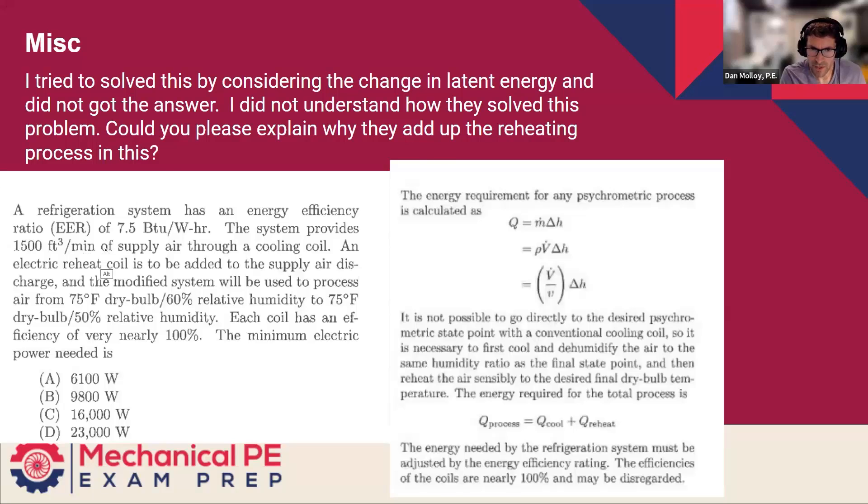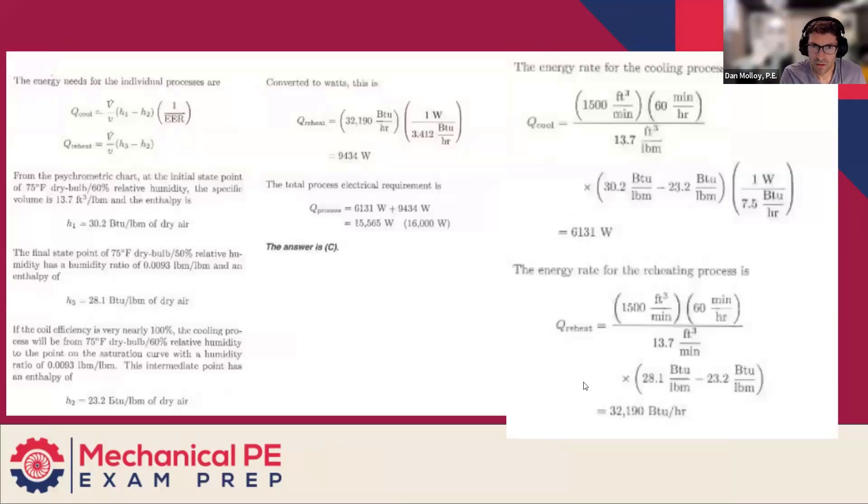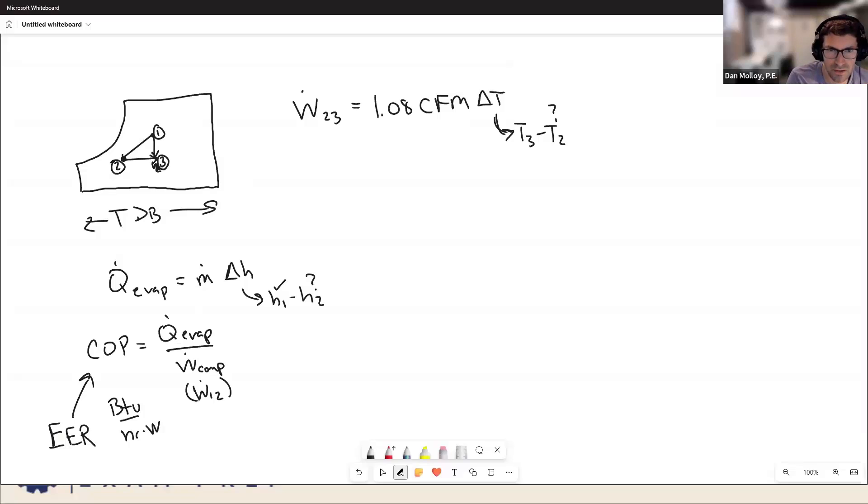So the only thing I'm missing is what are the conditions at state two? We know the CFM. Does the fact that we know the CFM do anything for us? Let's see what they did. First cool and dehumidify the air to the same humidity ratio as the final state point, and then reheat the air sensibly to the final dry bulb temperature. H1, H3. How'd they find H2? If the coil efficiency is very nearly 100%, the cooling process will be from 75, 60 to the point on the saturation curve with the humidity ratio of 0.0093. Ah! Okay, so they're assuming that this state two is all the way over here. All the way on the saturation curve. Move my two over there. Okay, so that's how they're saying this point is fully defined. So that gives us T2, that gives us H2, that allows us to find the amount of cooling that's being done.